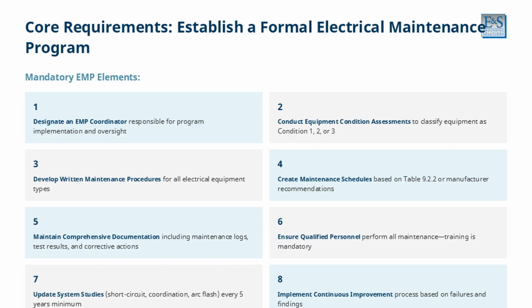Fifth, maintain comprehensive documentation including maintenance logs, test results, and corrective actions. Sixth, ensure qualified personnel perform all maintenance. Training is mandatory. Seventh, update system studies including short circuit, coordination, and arc flash analyses every 5 years minimum. And eighth, implement a continuous improvement process based on failures and findings.